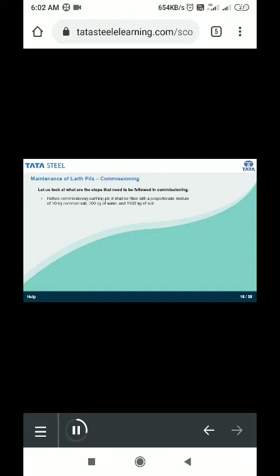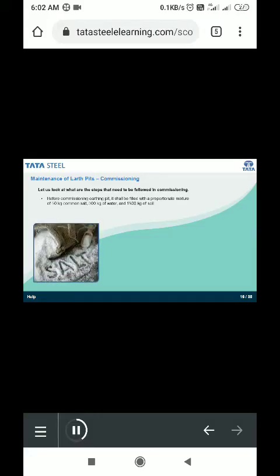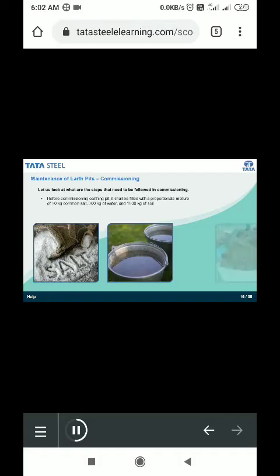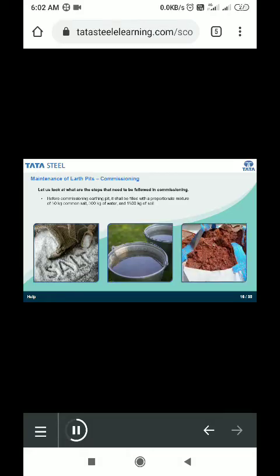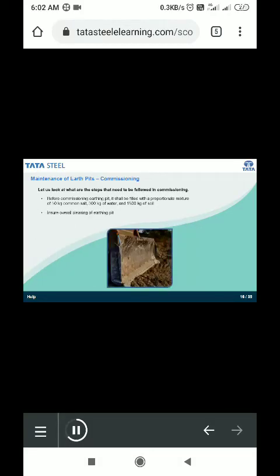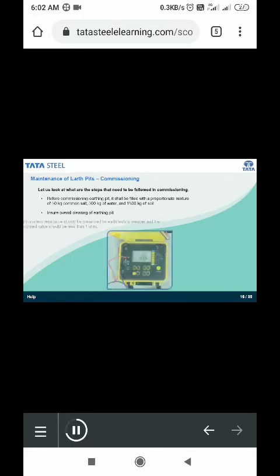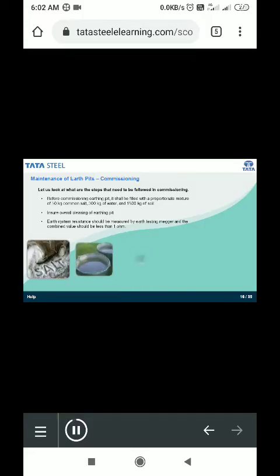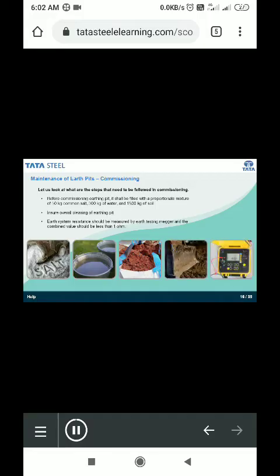Before commissioning, earthing pits shall be filled with a proportionate mixture of 50 kg common salt, 300 kg of water and 1500 kg of soil. Ensure overall cleaning of the earthing pit, and the earth system resistance should be measured by an earth testing meter, and the combined value should be less than 1 ohm. Let us move on to the next step, that is inspection.